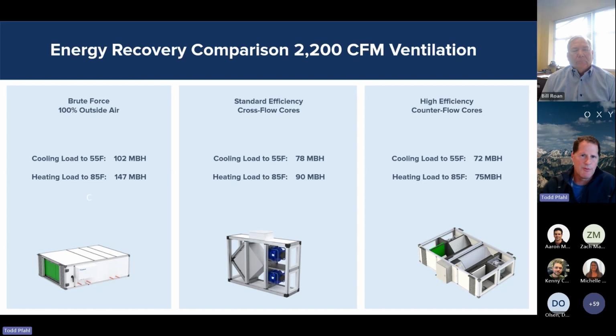So just to recap what kind of advantages you can get. Take an example of a 2200 CFM ventilation requirement for a building, just brute force. Reducing that 95-degree air in the summertime down to 55 degrees, or heating from 0 to 85 degrees, some sort of system in your building is going to have to do that with your ventilation air. So just that 2200 CFM is going to take about 100 MBH on the cooling side and 150 MBH on the heating side to be accounted for.